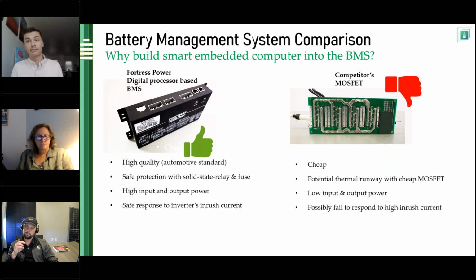With that you have this potential for thermal runaway, which is not good. You want a very good BMS that protects the battery cells and can handle high input and output power and respond quickly to an inverter's inrush current. Inverters are getting larger and larger, look at the Sol-Ark 15, the Envy, the Outback solution, because the typical solar system is getting larger as prices come down.